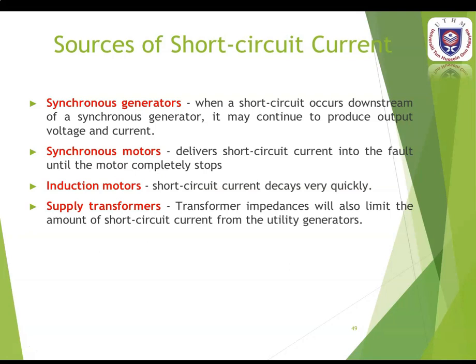For synchronous generators, when a short circuit occurs downstream, the generator may continue to produce output voltage and current. Generators are driven by turbines, water wheels, diesel engines, or other prime movers. When a short circuit occurs, the generator will continue to produce voltage at its terminals as long as field excitation is maintained. The generator voltage causes large fault current limited only by the generator impedance and circuit impedance between generator and fault point.